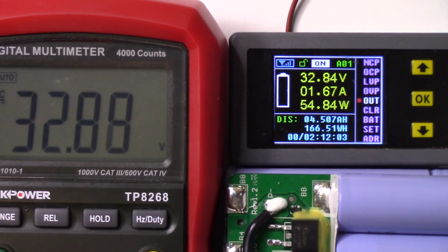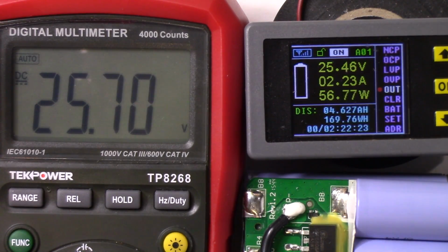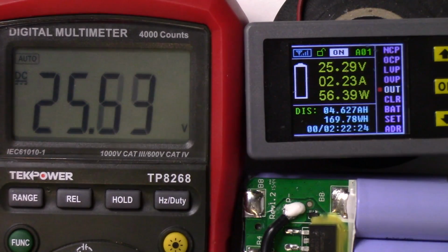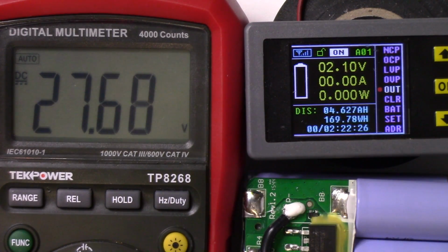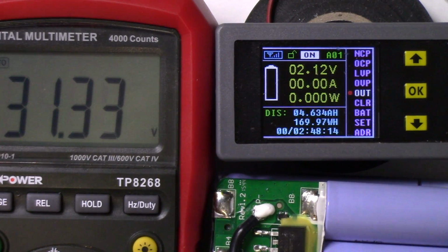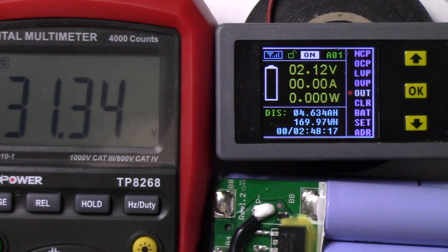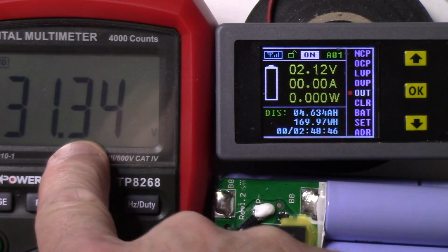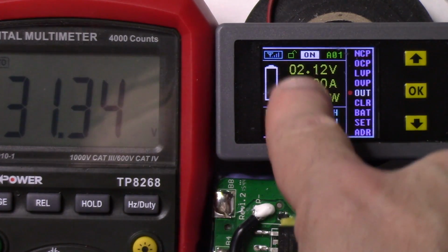You saw where that cut off — it was 25.53 volts. I let the video trail after the capture so you can see that almost instantaneously, even while the beep on my inverter was still going off, the voltage went right back up to 25.89. You can see how the battery recovers quickly. Now it's at 31.34, but I left the circuit intact, so you can see the disconnect is still here, because the voltage off the pigtail on the battery pack is at 2.12 volts.